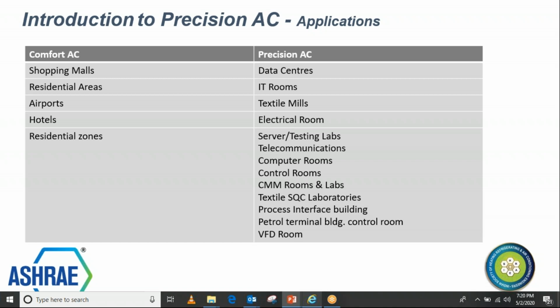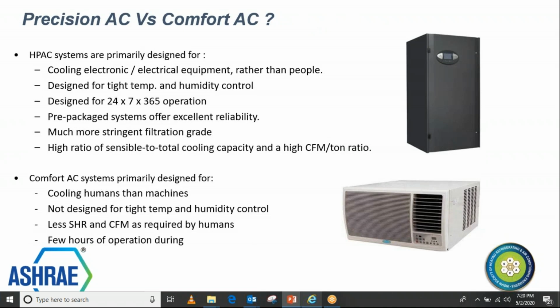And then we move forward now in understanding how each of these designs works, the comfort design, what the basic concept is, and what the concept behind precision AC is, which makes it different in terms of design. So all HPAC systems, and when I say HPAC, it is high performance precision air conditioning systems, are also known as close control cooling systems. They are all designed around the high sensible heat ratio. So cooling electronics is the basic fundamental here. What makes the difference is the sensible heat ratio, the design of the cooling coil and the airflow, and the temperature and humidity control.